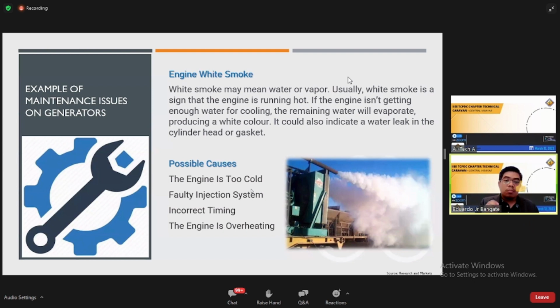White smoke may mean water or vapor. Usually white smoke is a sign that the engine is running hot. If the engine isn't getting enough water for cooling, the remaining water will evaporate, producing a white color smoke. It could also indicate a water leak in the cylinder head or gasket. Okay? So possible causes: the engine is too cold, faulty injector system, incorrect timing, or the engine is overheating. So those are what you should check when you see your generator emitting heavy white smoke.